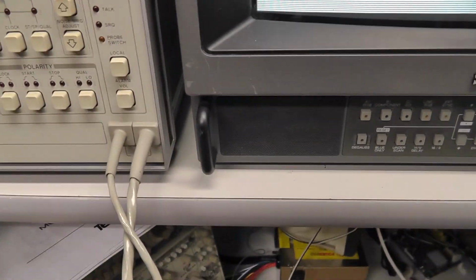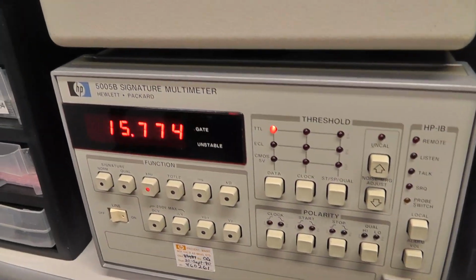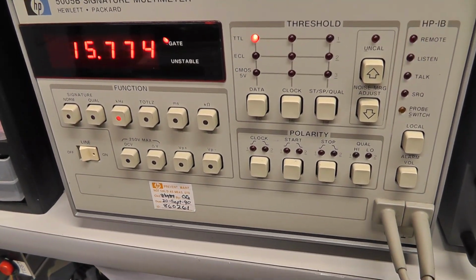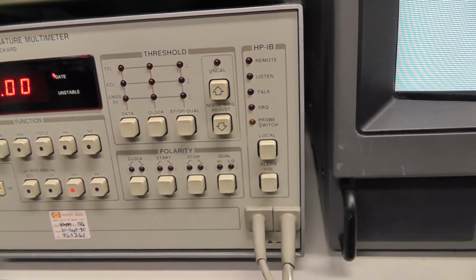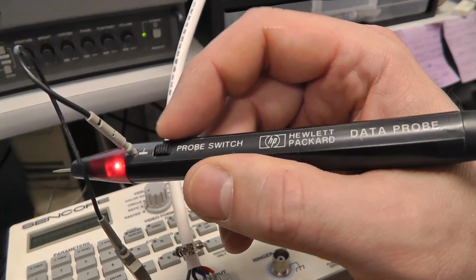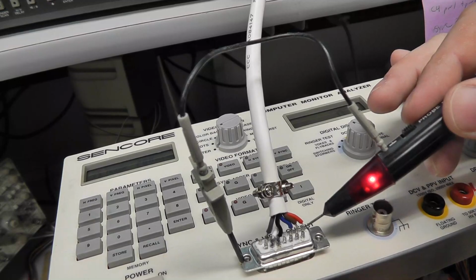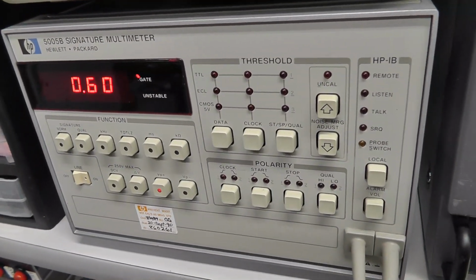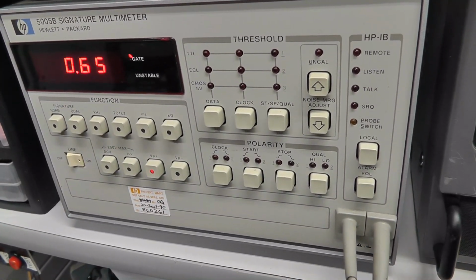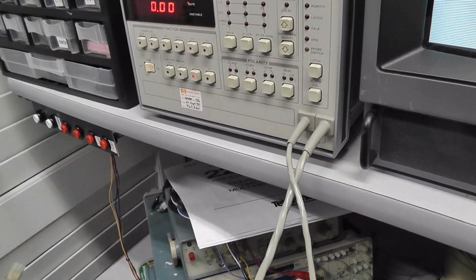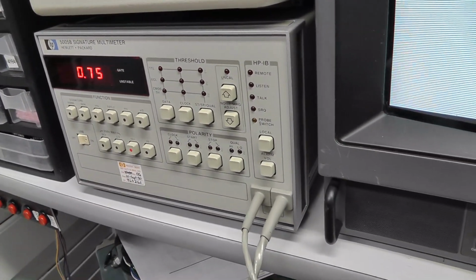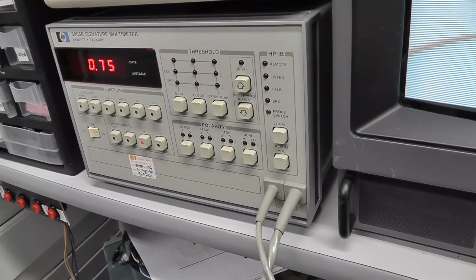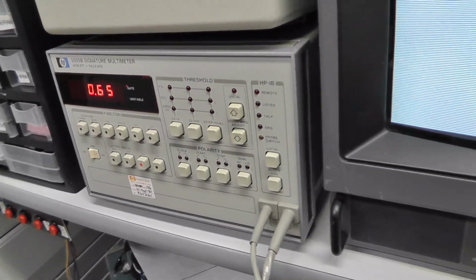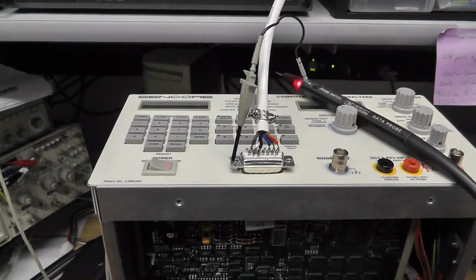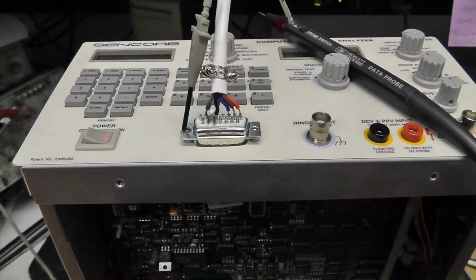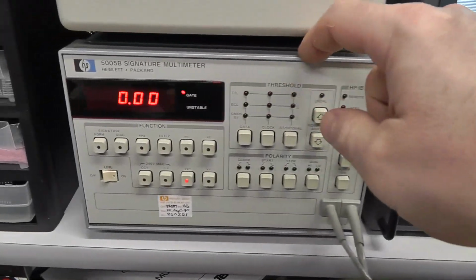Let's see here. I put it on kilohertz, so I'm measuring composite sync, I guess. And I'm getting 15.7 kilohertz on composite sync, and I go to voltage peak. I think you need to hit this probe switch to enable this switch, because now my light's blinking. I haven't read up on this one. My voltage peak on the red is now 0.605, so I could definitely get slightly different readings than my other one. This is the green, 0.75, and blue is 0.75. So I'll adjust my red and green down to 0.7 and this one up. Try to get everything at 0.7 based off of my 5005B.